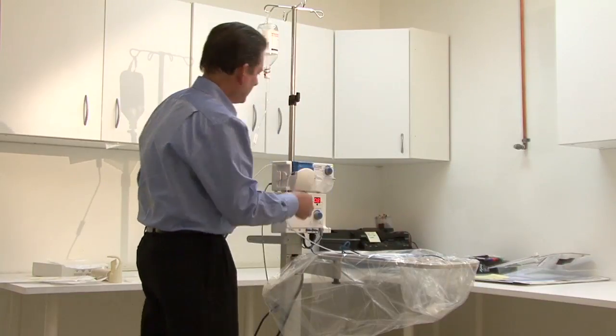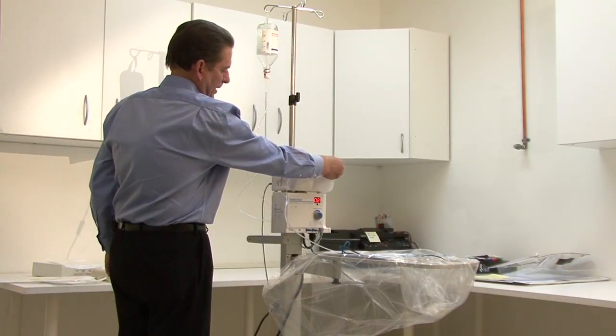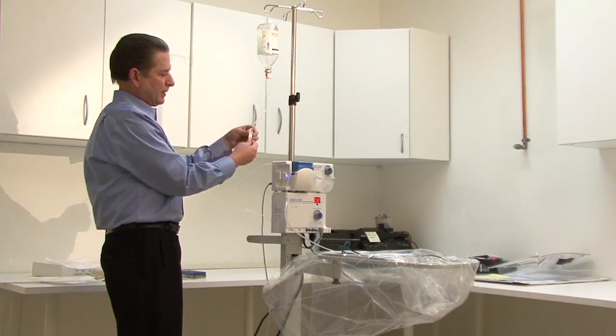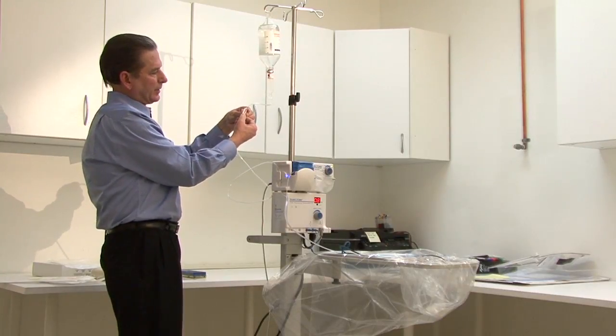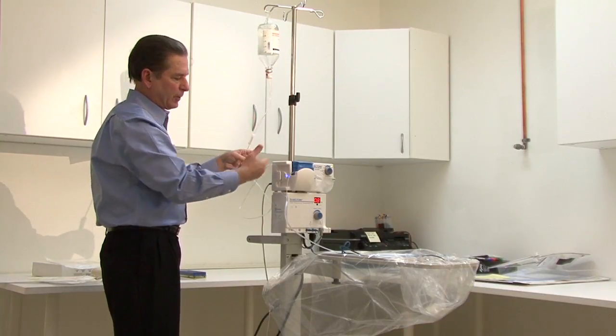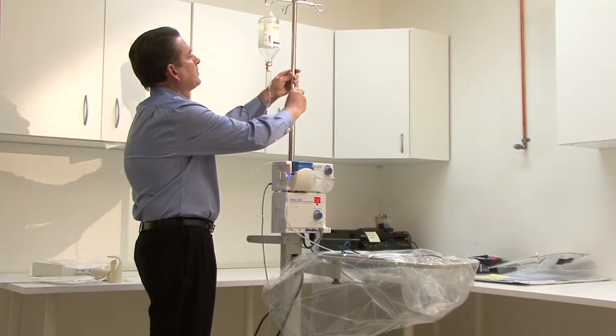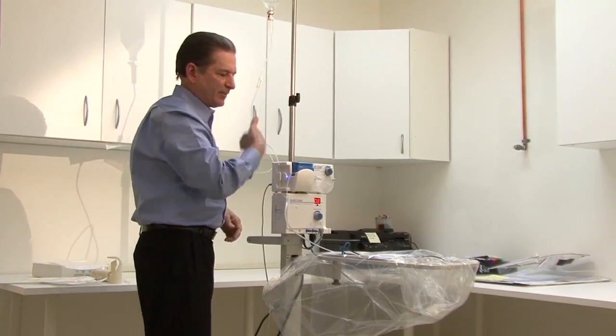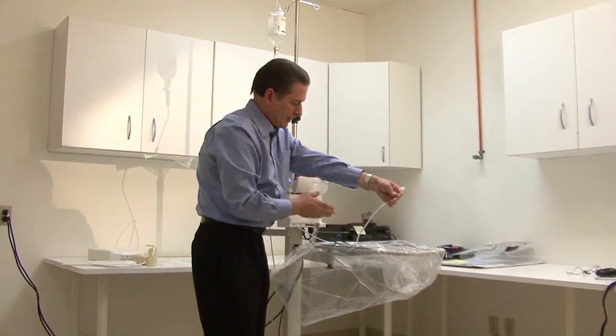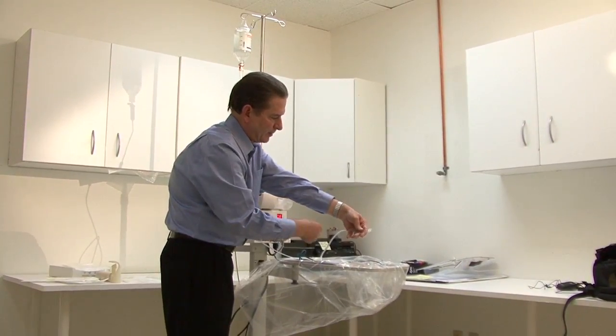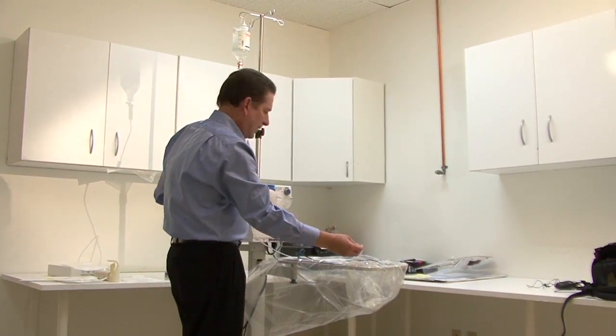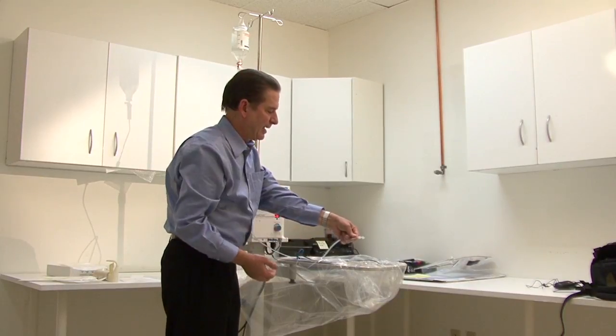And what we're going to do is we're just going to go ahead and turn on the prime, which opens the irrigation flow. Remember, we have our clamp closed. We can open our clamp and we'll start the flow of the BSS. We can raise the bottle a little bit. And we're just going to flush the irrigation line really good. Make sure all the bubbles and the fluid just flows out the irrigation line. And that'll happen very quickly if we don't connect the handpiece.